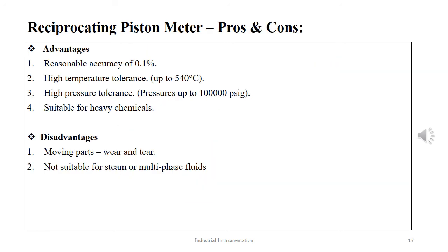The advantages of the reciprocating piston flow meter are: reasonable accuracy of 0.1%, very high temperature tolerance 540 degrees Celsius, very high pressure tolerance 100,000 PSIG, and suitability for heavy chemicals. The limitations are moving parts and therefore chances of wear and tear are high, and not suitable for steam or multiphase fluids.